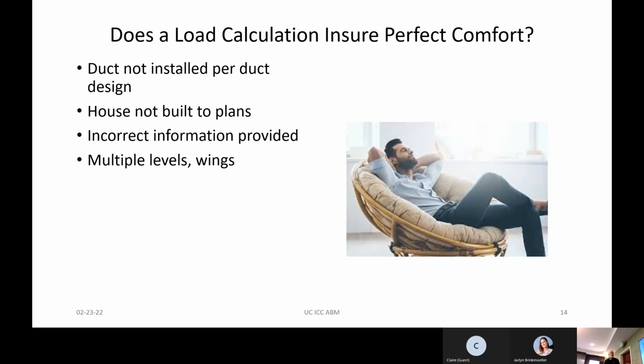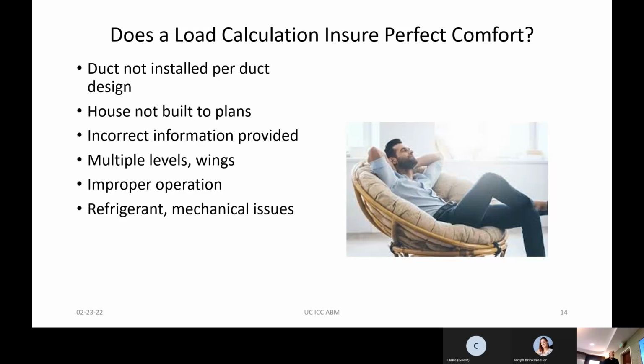Just requiring a load calculation doesn't mean the homeowner isn't going to have a complaint—improper operation, refrigerant and mechanical issues. It's easy to blame the inspector for making us do a load calculation, when in fact something else is wrong: the charge is wrong, the line set is kinked, there's something wrong with the system.